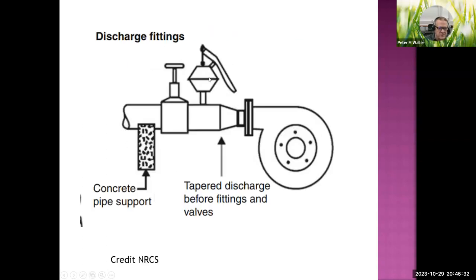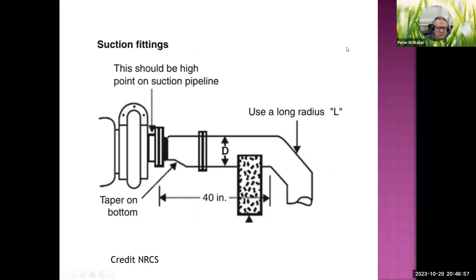On the discharge side, a tapered discharge fitting helps save energy during diameter transitions. A priming pump is used to draw water up, followed by a discharge valve. On the suction side, the eccentric reducer with a long-radius elbow is specified. Irrigation companies typically fabricate these fittings in-house by welding.